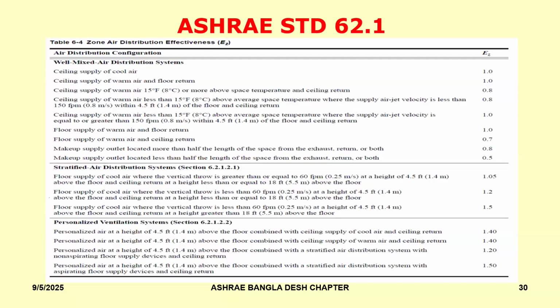For example, the one that's most commonly used is a mixing air system. So in the mixing air system, the air will be supplied from the top of the room, and then it mixes in the entire space, and the return air is then collected back on the ceiling, or it could be collected at the floor level. So depending upon how the air is being distributed, you have something called the zone air distribution effectiveness. So if the zone is well ventilated or the air is absolutely well mixed, then the ventilation effectiveness will be 1, which means if I calculated CFM based on number of people and the area as 500 CFM, then I simply divide that by 1. That is for a well mixed air distribution system.